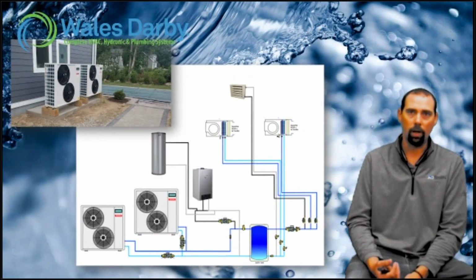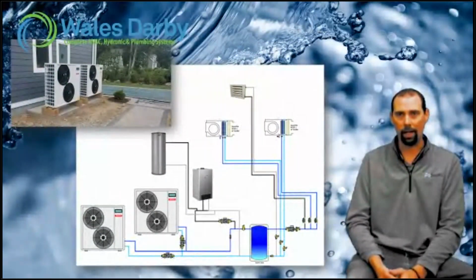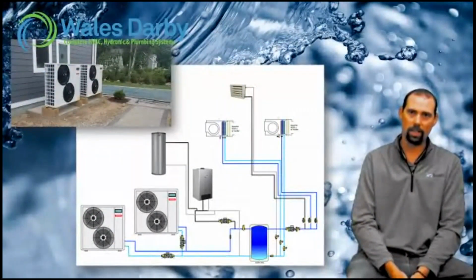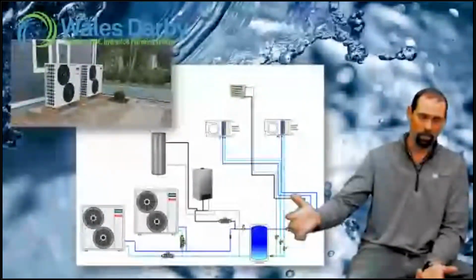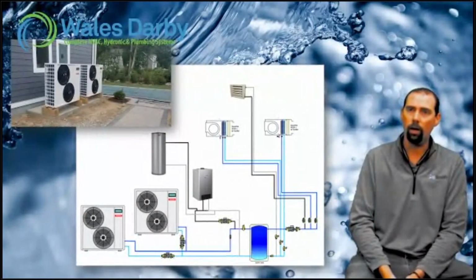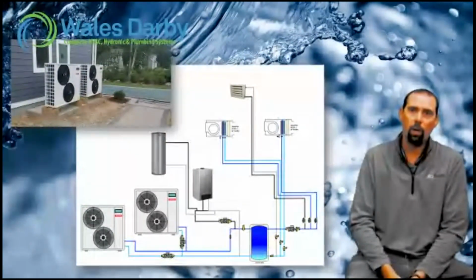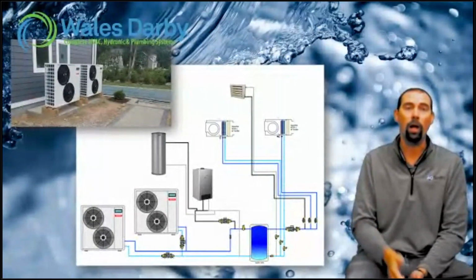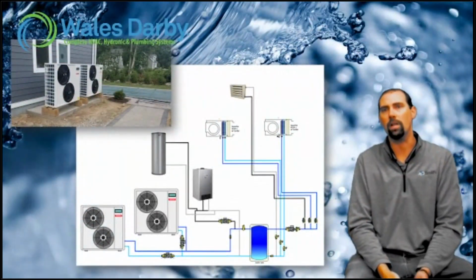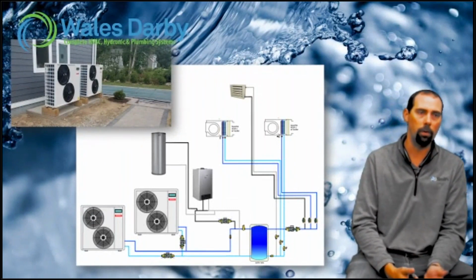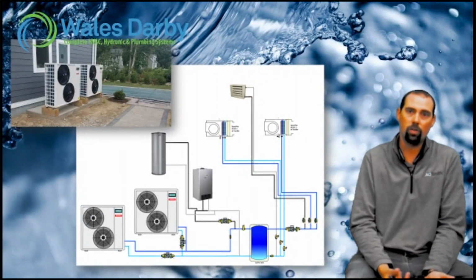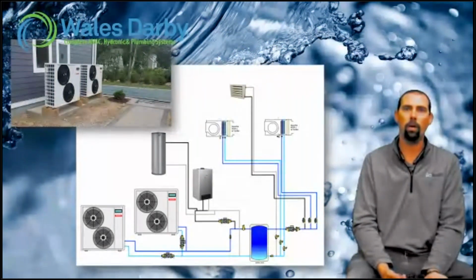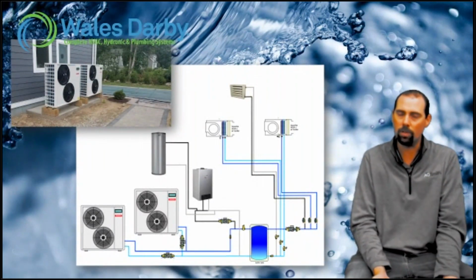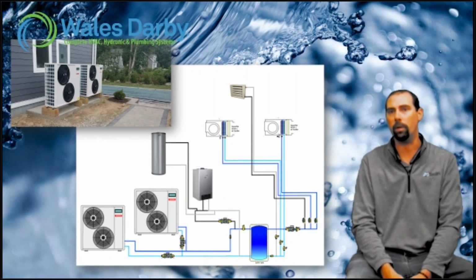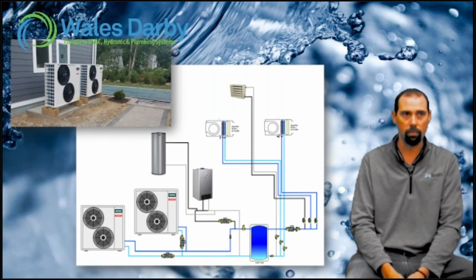So yeah, we might have to run a bigger pipe. We do have some underground piping, we call it EcoFlex from Uponor. That's a direct burial, pre-insulated pipe, cut basically to order, custom lengths. We don't have to be just 50 feet away, we're not limited like refrigerant line sets as far as lengths and height requirements. It's creativity, how far do you want to go? Yeah, we have a pump for it. Is there a cost? Absolutely, but we have the abilities and capabilities with all of our pumping to probably hit that.